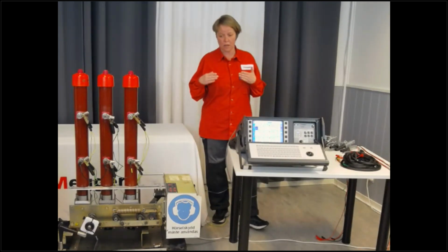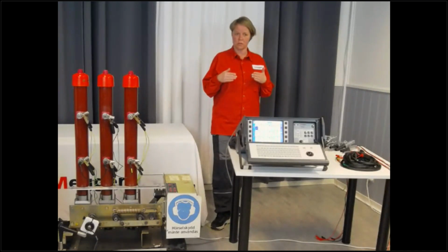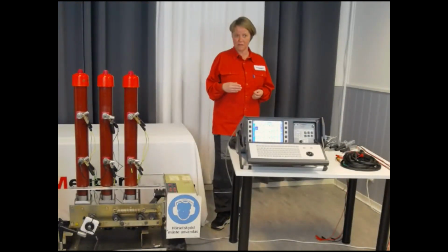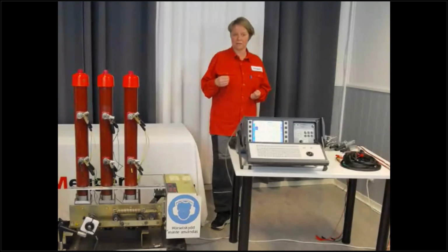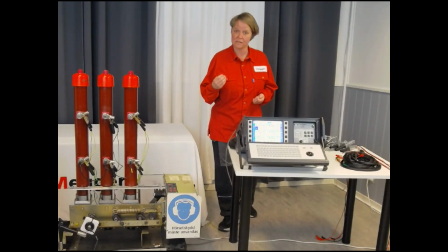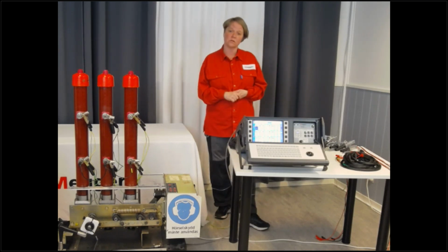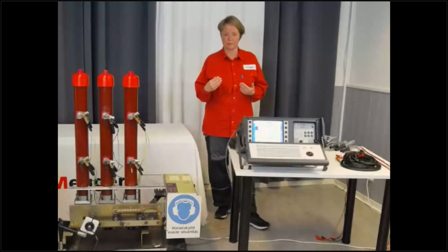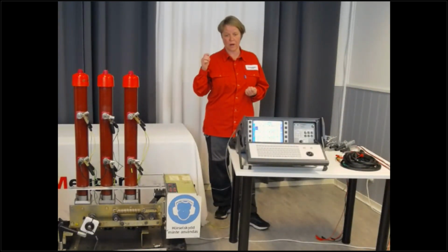And also, I've been around where we measured on a GIS where we had no connection points at all inside the switchgear room. So we had to go outside and connect up on the flanks of the bushings in the house, the bushing out to the lines. There we grounded outside, connected there, and connected to grounding in the structure.